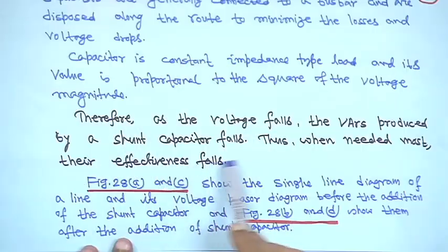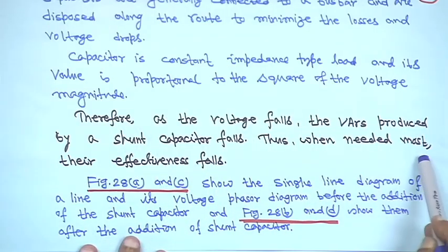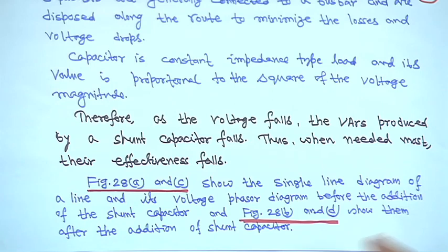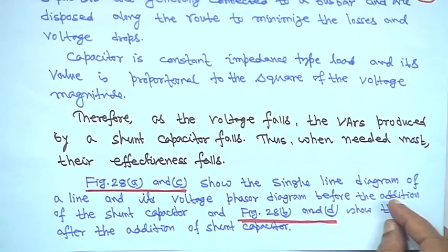As the voltage falls, the VARs produced by the shunt capacitor fall — thus, when reactive support is needed most, the effectiveness of the shunt capacitor actually falls.